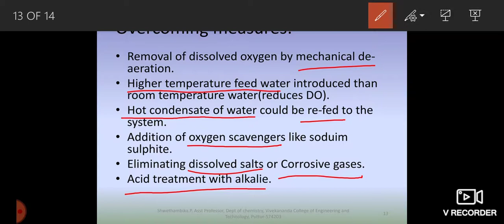Then fourth approach is addition of oxygen scavengers. So any chemical which, added in small concentration, removes another chemical, you can call them scavengers. So example given is sodium sulfite. It immediately combines with oxygen molecules and oxygen could be removed. Also we can remove the dissolved salts because they would cause the generation of acids, and by chance any corrosive gases are there, that also could be removed when the process of boiling the boiler feed water is started. Also, if by chance acid is generated, it could be treated with alkali. They are counter chemicals. Acid and alkali react, so that alkali is base, so acid and base would react so that it could be neutralized and corrosion could be avoided.